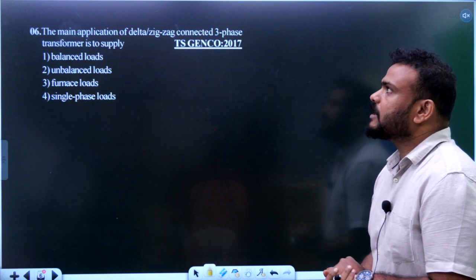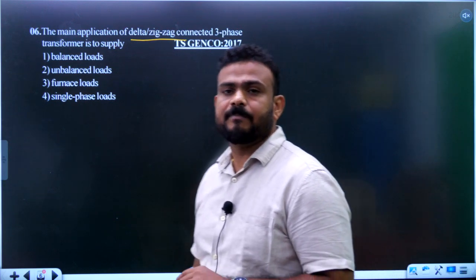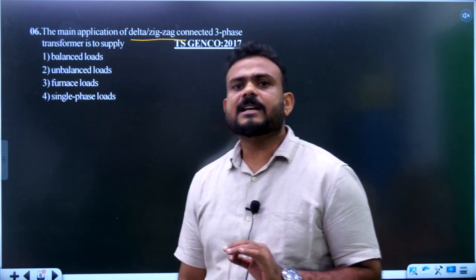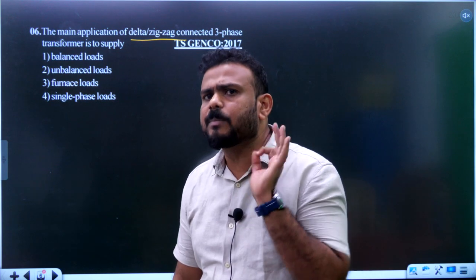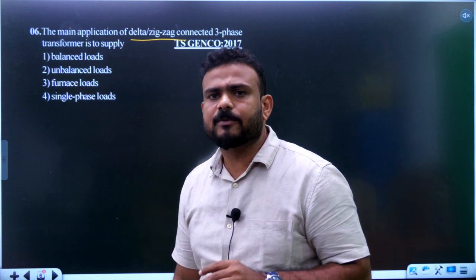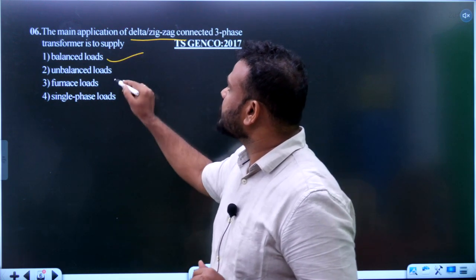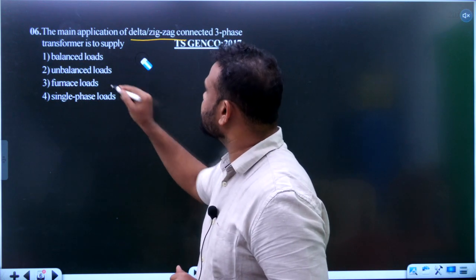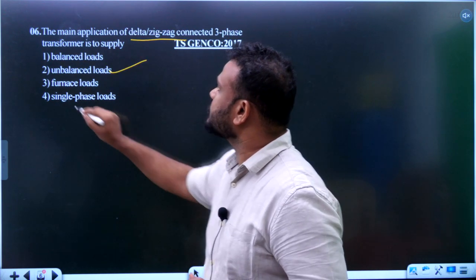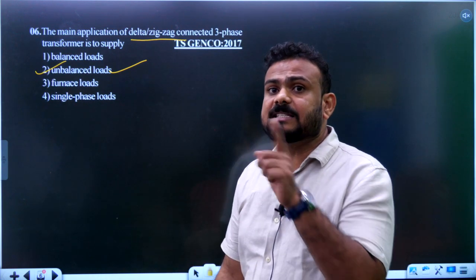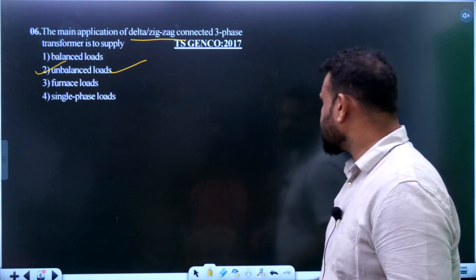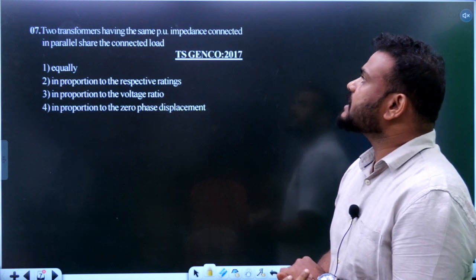Question 6: The main application of a delta-zigzag connected three-phase transformer is to supply what type of load? The zigzag connection provides a neutral point. With a neutral point available, it is easier to connect unbalanced loads. Therefore the answer is unbalanced loads — option 2 is the right answer.